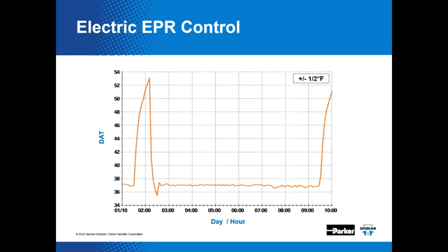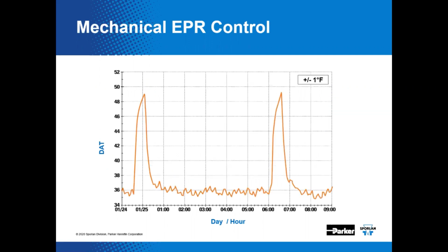Now let's compare the performance of this method with a couple of the other methods we've discussed in previous webinars. Here's the mechanical EPR control. It's pretty darn good itself, still pretty good, plus or minus about 1 degree F, but not quite as quick a recovery coming off a defrost. It does vary, like the plus or minus 1. So not quite as good, even though this is a very effective and efficient way to control temperature.